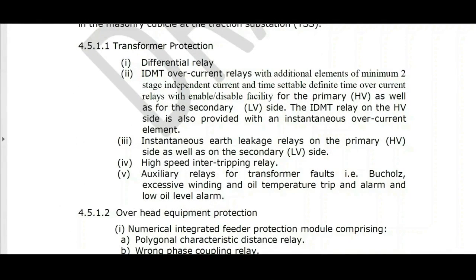That is between the CTs. If there is a fault outside the transformer, away from the CT, and if the magnitude is high, then we provide a time delay and wait for some other relay to operate. If no relay is operating, we will trip. This is called IDMT, inverse definite minimum time. It means the greater the fault current, the lesser the trip time. The lesser the fault current, the greater the trip time. This is called IDMT.